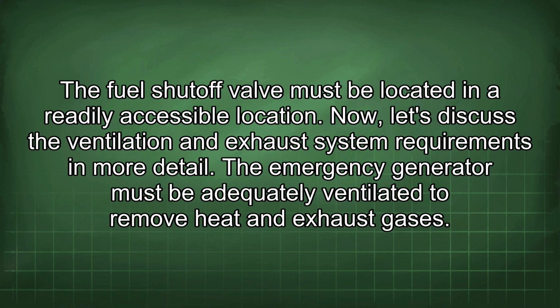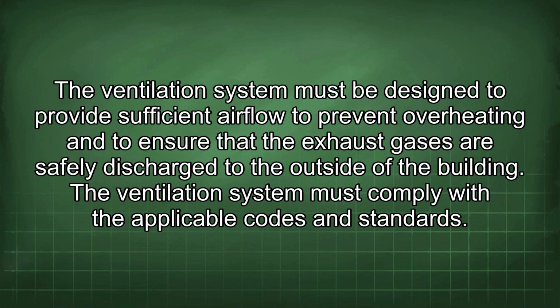Now let's discuss the ventilation and exhaust system requirements in more detail. The emergency generator must be adequately ventilated to remove heat and exhaust gases. The ventilation system must be designed to provide sufficient airflow to prevent overheating and to ensure that the exhaust gases are safely discharged to the outside of the building.